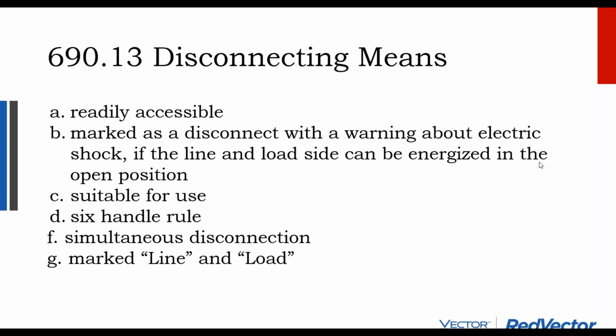Okay, so there does have to be a disconnect switch for a solar array. So that disconnect switch has to be readily accessible. And a recent 2020 change is that if your main disconnect switch for the array is not outside the building already, you have to have an additional disconnect switch outside the building for the fire department. It's been mandated in almost all jurisdictions without being part of electric code for quite some time. So in most jurisdictions already, you have this knife switch disconnect outside the building to turn the array off. But now, not necessarily a knife switch, but a disconnect switch has made it into code today. So readily accessible means you shouldn't have to climb up a ladder to get to the place.